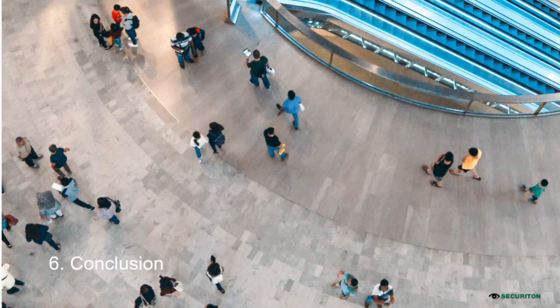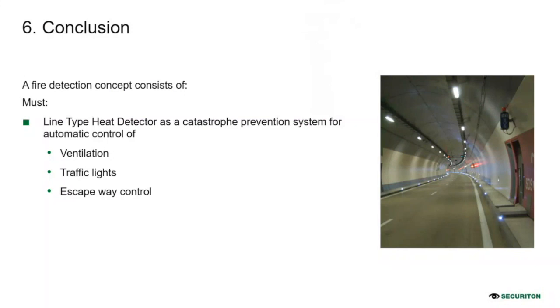Then coming to the conclusion, we see the fire detection concept consists of line type heat detectors. This is a must to trigger especially the ventilation system, the traffic lights, the escapeway control, and many other systems. So the fire detection system has a very important role inside the whole concept, the whole design of a road tunnel.